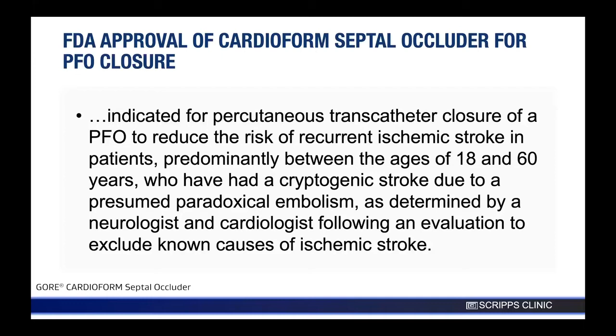All right, so let's talk about the Cardioform septal occluder and its characteristics. The Cardioform septal occluder is essentially a platinum-filled nitinol wire frame covered with expanded PTFE that when fully deployed assumes a double disc shape in which each disc has identical diameter. GORE became GORE because of its application of ePTFE, and so the Cardioform is no exception. So you see here this double disc device. We'll go into some details about how the discs are formed. This is what it looks like fluoroscopically on your far right with 2 discs and 3 eyelets.